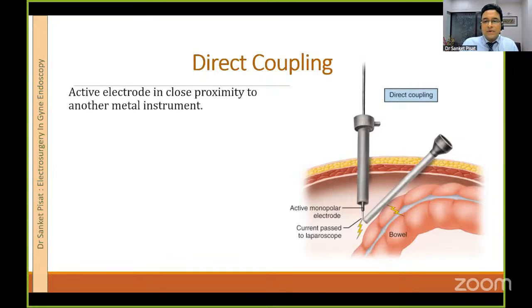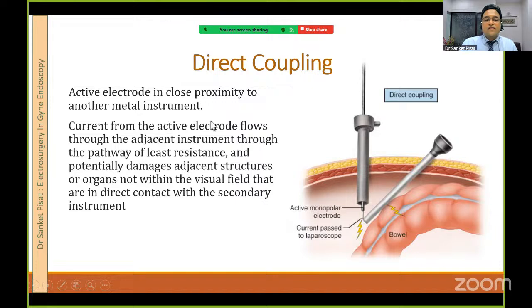This is direct coupling. Imagine that there is an active electrode in close proximity to another metal instrument. This is the active monopolar electrode. I plan to work using this electrode, and this is another metallic instrument in close proximity. What is happening? Current from the active electrode flows through the adjacent instrument through the path of least resistance. Ideally, what should be happening? Current from here must flow down into the operated area and then back to the return electrode.